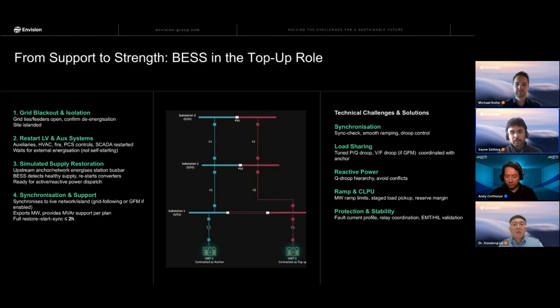So, the technical challenges for the top-up service. Again, this is not very complex compared to the anchor, however, this also needs to be planned in a proper way during the design phase of the project, on how we are going to meet these requirements while operating the BESS as a top-up service. The synchronization part is a key thing, how we synchronize with other systems in the transmission network. And for load sharing, when we are operating in GFL, we need to tune the PQ curves in the system, whereas in grid forming, we have to tune the VF droop curve in a way that we share the load depending on the capacity of the systems.